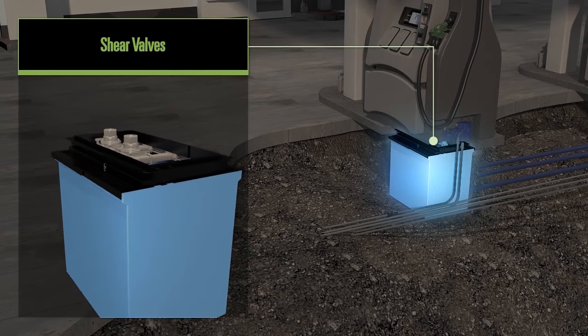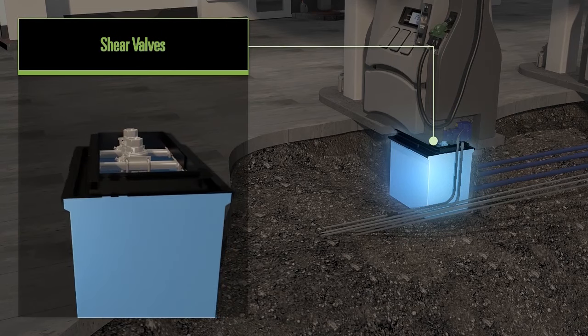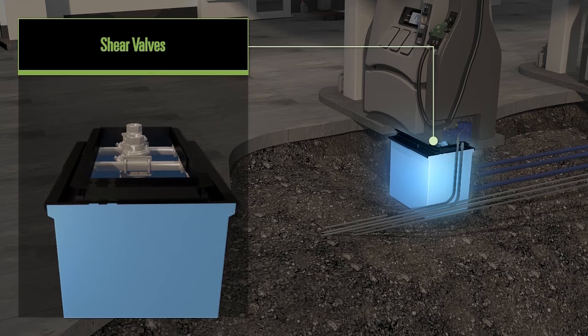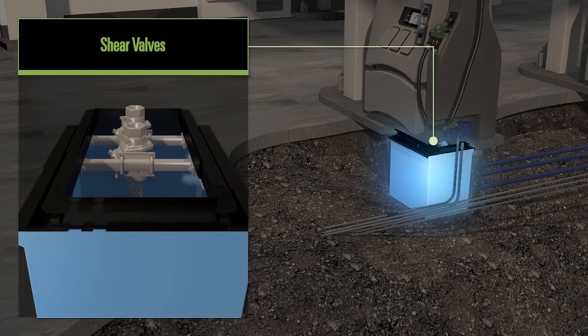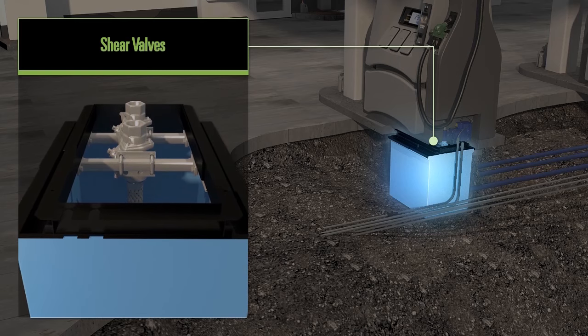As for dispenser safety, if one is hit, the shear valve is designed to break in a controlled manner and a poppet inside the valve will seal off the tank, preventing the product from endangering the customers and the surrounding environment.